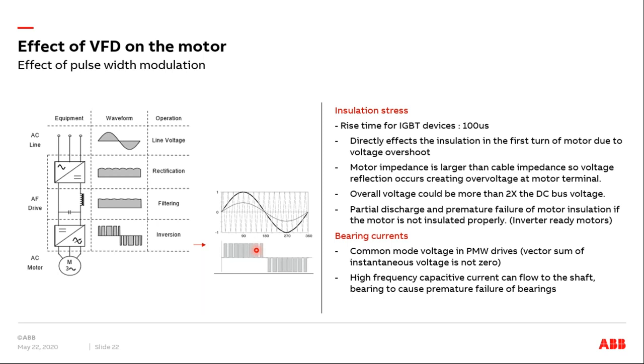So if you send a fast switching pulse to this motor, which has a high impedance, then as in a transmission line, you have a reflection of the wave. Because of this reflection, the voltage the motor sees can be more than two times the peak of the DC bus voltage, or the peak of your supply, basically.